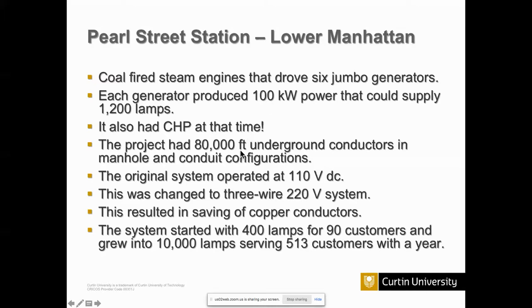The project had about 80,000 feet of underground conductors in manhole and conduit configuration, so they will pass through manhole and then through conduit. The original system was 110 volt DC, but then he realized the voltage drop is too much. So it was changed to a 3-wire 220 volt system, so you will have 110, 0, minus 110. So you could use both sides of that, and these resulted in saving of copper conductors.